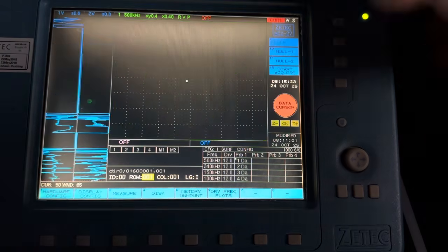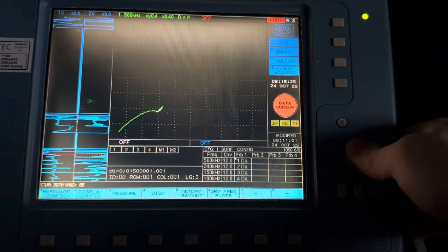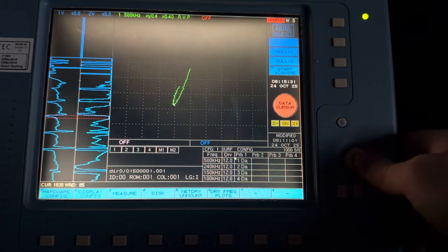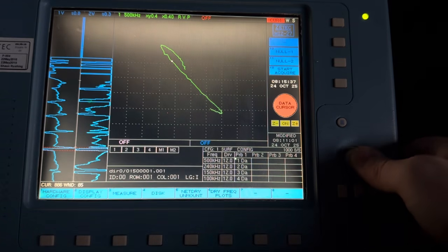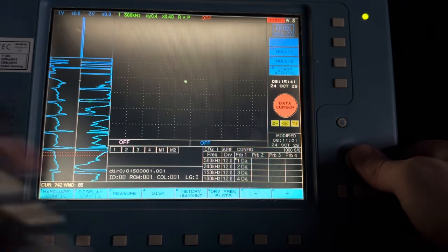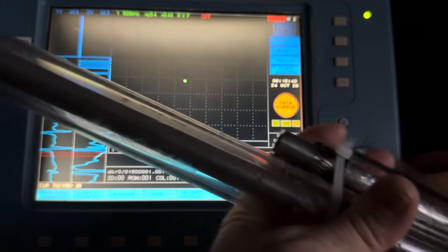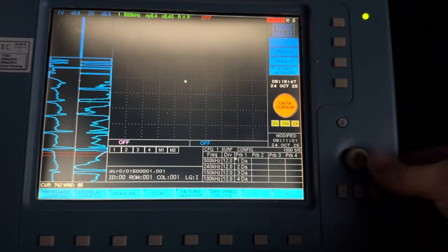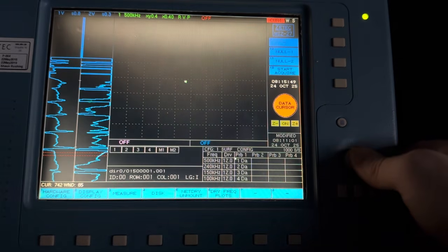Now I'm going to stop the tester. That's the data up here. Let's see here, where is it? Right here. So the earliest in time data is down here. This is useful when you have a calibration standard drawing. You can look at it, and then you can hold up your calibration standard. If you can locate where the 100% hole is based on your drawing, then you can figure out what all the other flaws are.